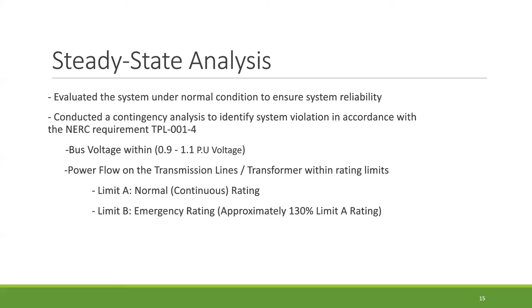TPL-001-4. And precisely in this document, it states that our bus voltages must be within the range of 0.9 and 1.1 per unit voltage. And the power flow over transmission lines or transformers must be within the ratings of limit A and limit B. And so limit A will be the normal continuous rating, and limit B will be the emergency rating, which is approximately 130% of what the limit A rating is.